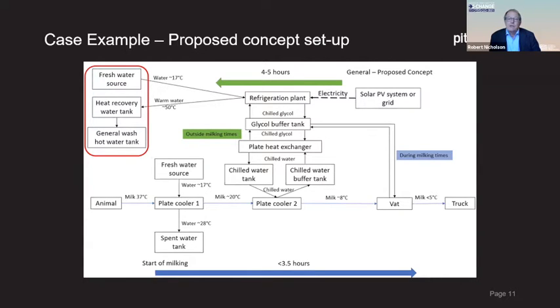Using that refrigeration system brings an additional cooling stage to the milk prior to entering the vat. Previously, milk came from the animal at 37 degrees, went through freshwater heat exchange to 17 or 20, then to the vat. Now it passes through an additional pre-cooling stage, bringing it down to about 8 degrees before entering the vat, meaning the vat only needs to cool a further 3 or so degrees to get below 5 and maintain that temperature until pickup. This new process saves a significant amount of cooling time, utilises a renewable energy resource to do so, and is much better for the farmer.